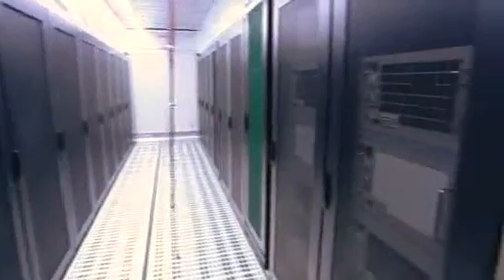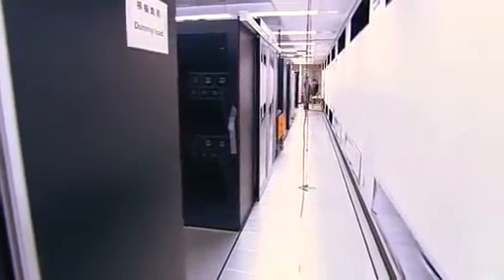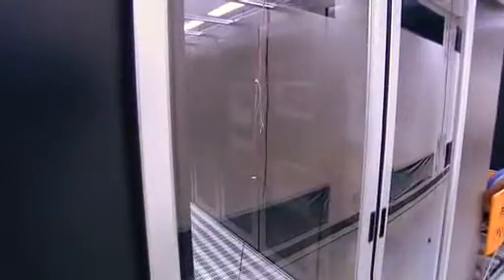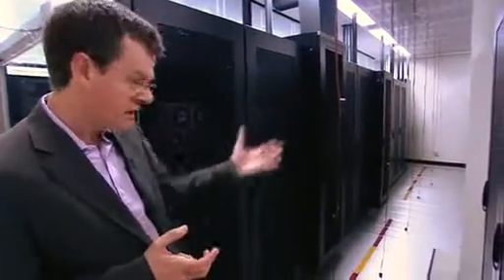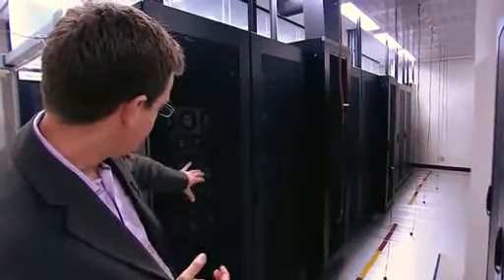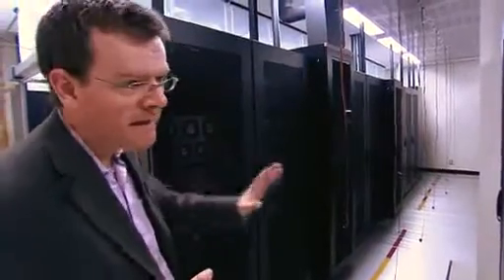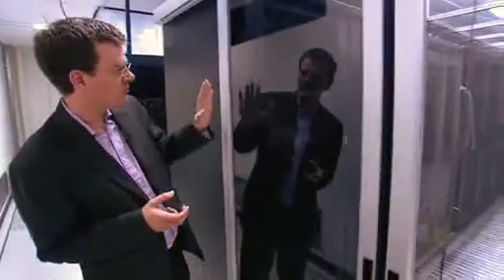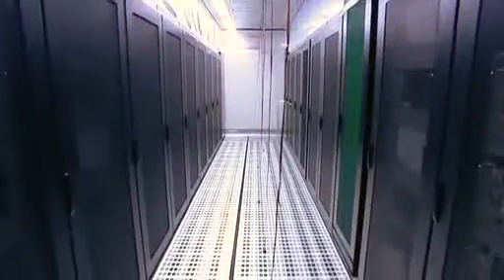ICT equipment. With 40% of data centre power use taken up by air conditioning, NTT has devised 2 solutions that can reduce this unwanted burden. The first is known as aisle capping. This optimises airflow within data centres by designating discrete channels. You have the hot channel for the hot exhaust air generated by the racks of equipment, and next to the hot channel you have separate and sealed cold channels, which creates the ideal operating environments.